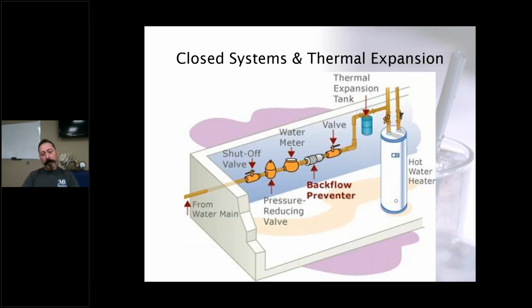Also, if you install a backflow preventer on a main water supply, and there's a hot water system or a heating system downstream of that device, you've locked that expansion in. When that hot water gets hot, it needs a place to expand, and with a backflow preventer it can't expand anywhere. So that hot water will get heated and it'll back pressure hot water down the cold line. If we don't allow for that expansion through a thermal expansion tank, then the hot water tank is going to be under a lot of stress. It's going to start discharging under the temperature and pressure relief valve, and people will start replacing hot water tanks and all kinds of issues.